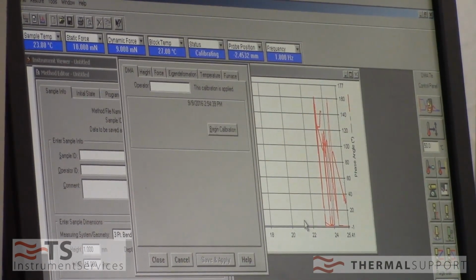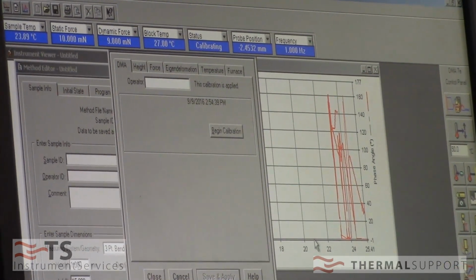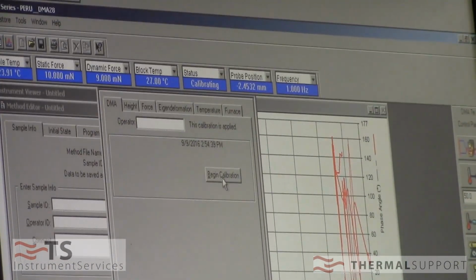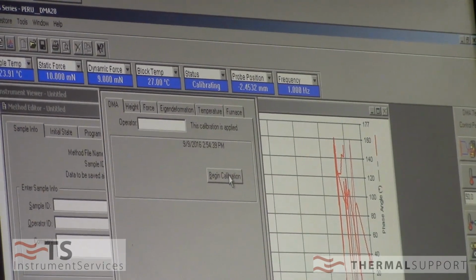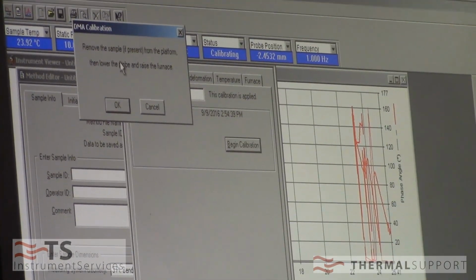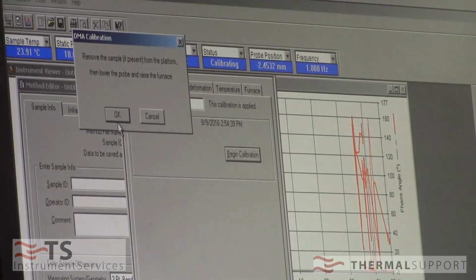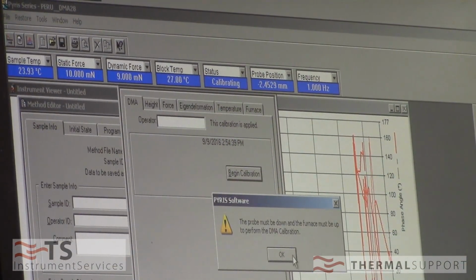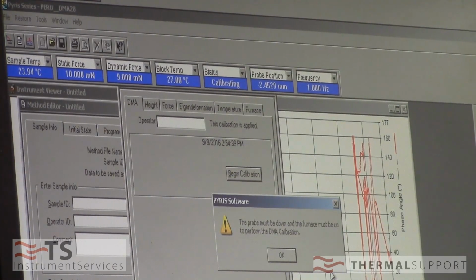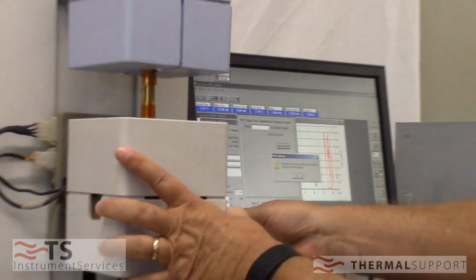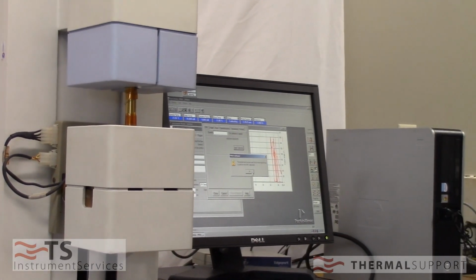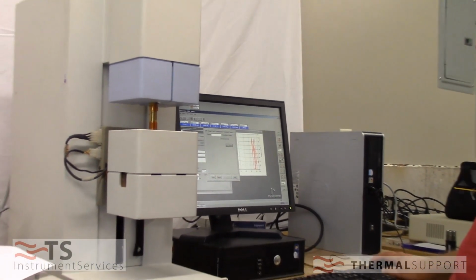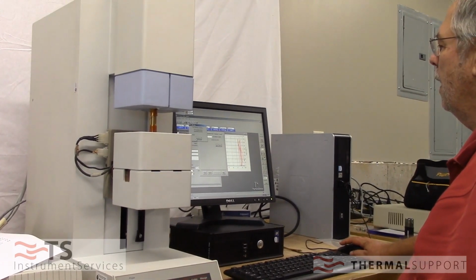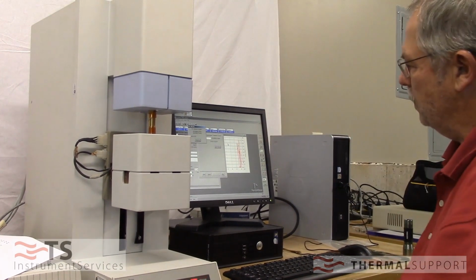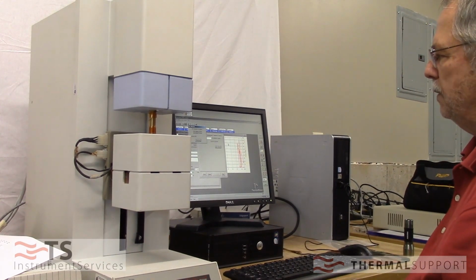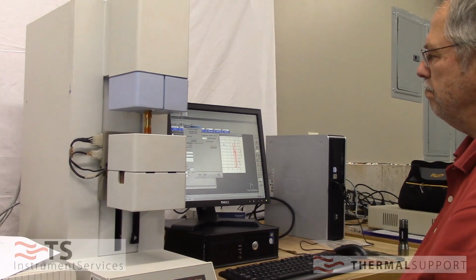So now we're back. We've named the file. Everything's back to where it started, and we're going to do our begin calibration. So begin cal. Make sure your samples are on the probes on the platform. Furnace must be up. I know I always forget that. There you go. And the screen says 25 minutes. Pretty much it. We'll be back.